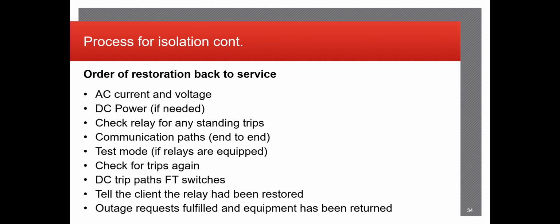For restoration, to put the relay back into service, you pretty much just go the complete opposite way. You start with the currents and voltages, power up the relay. Always check the relay for any standing trips, meaning once you put power into the relay, you look at it, you see if anything's wrong before you put those DC trip paths back in. If you put one of those DC trip paths back in and there's a standing trip on that relay, it will immediately operate that piece of equipment and cause another outage that you did not plan on, and the client does not like that.